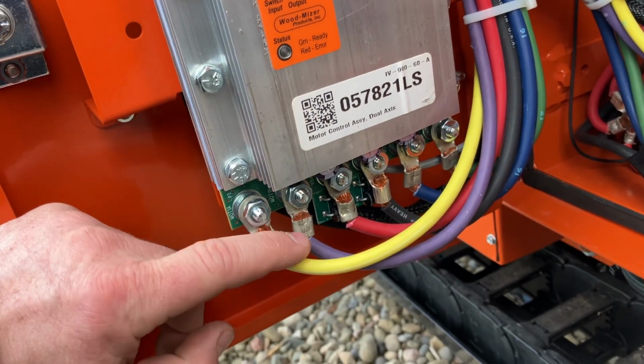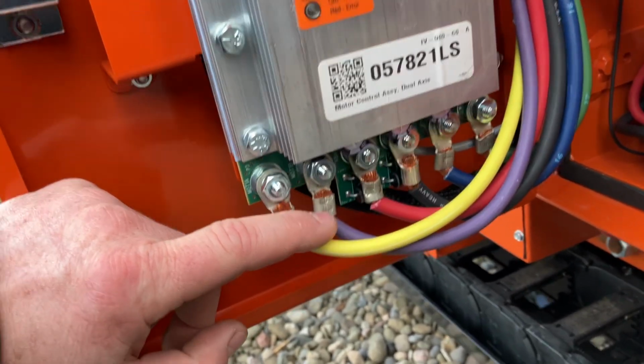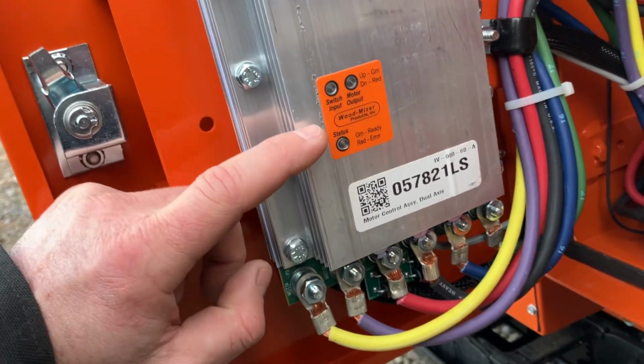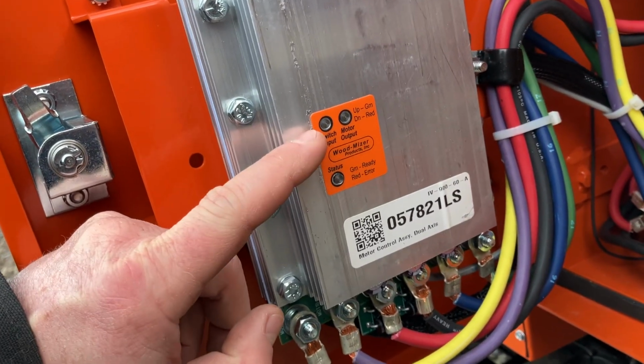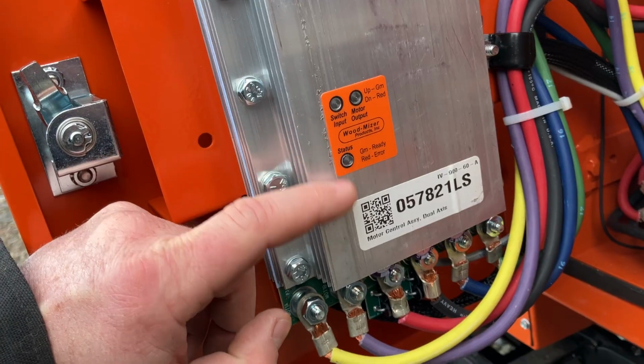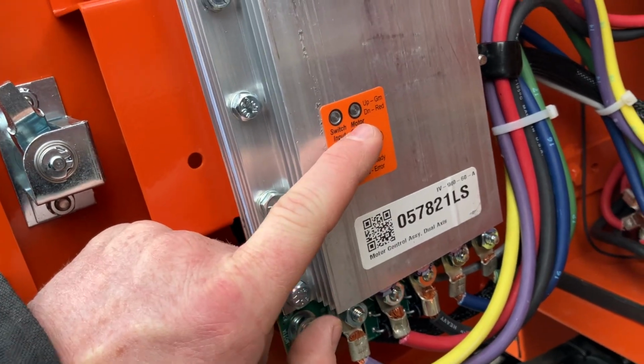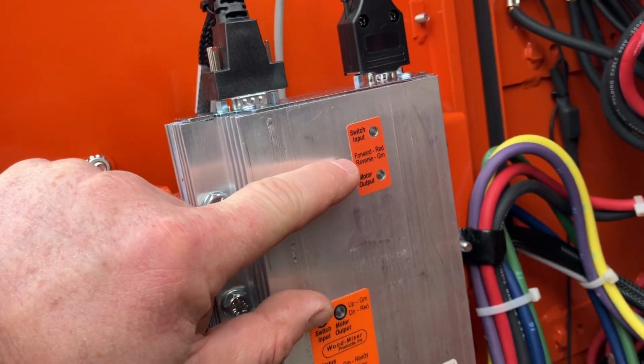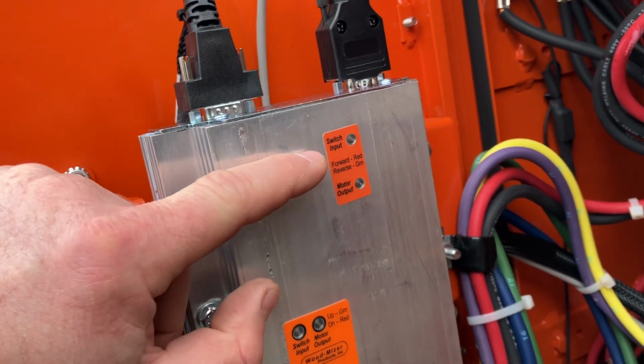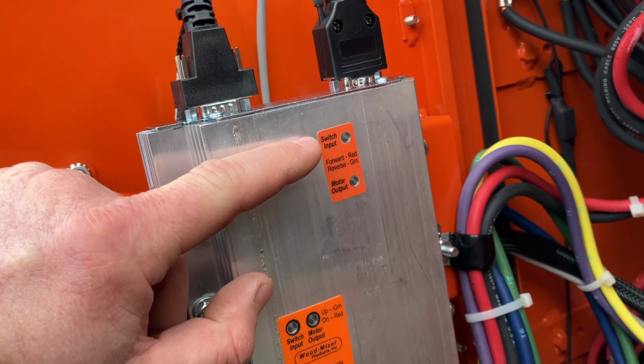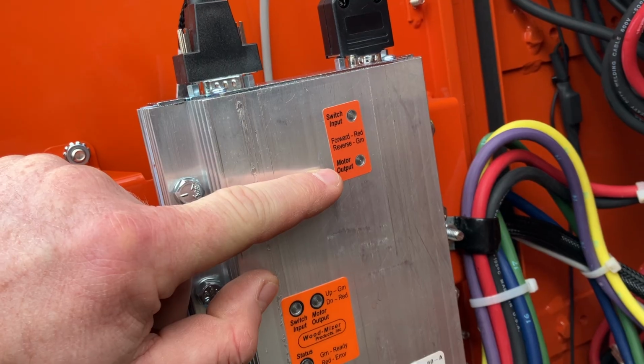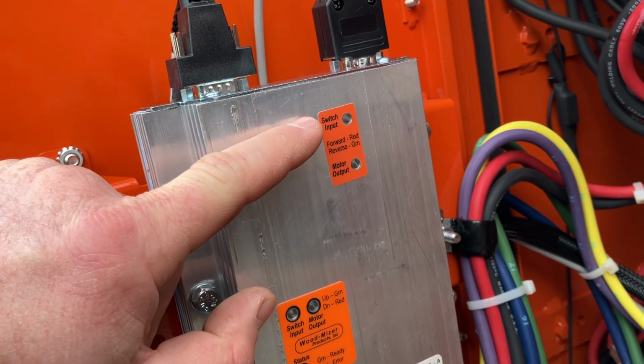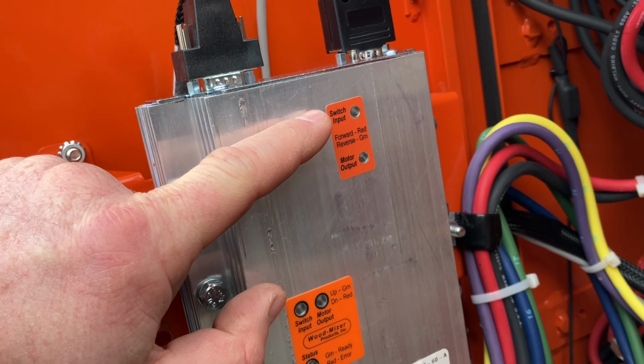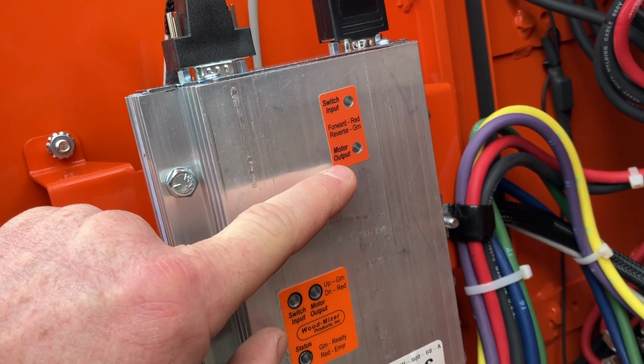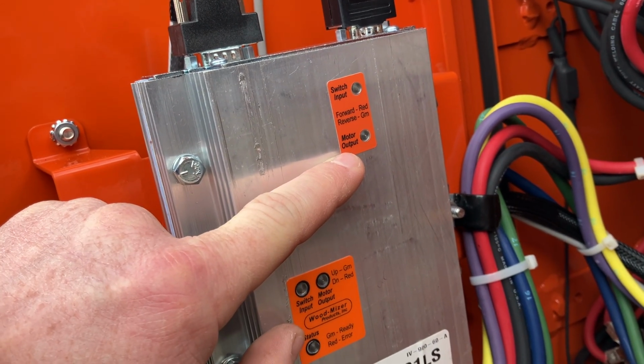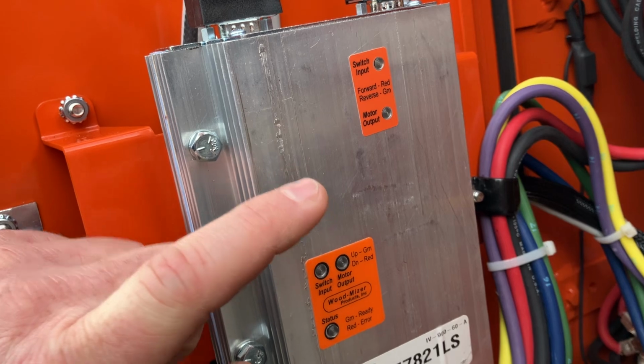With this situation, when I would hit the up and down, the motor up and down, lights would come on, and the output motor light would fire here. When I would go in reverse, it would come back. The switch input picked it up, motor output picked it up, but when I went to go forward, the switch input light came on, which told me that the drum switch was working, but the motor output light never came on. So we know that there was an issue with the control power.